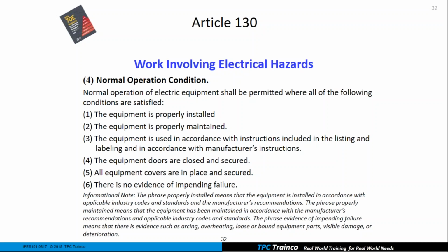Number 3 is the brand new one, and if you're familiar with the National Electrical Code, this did come out of 110.3(B) of the National Electrical Code: the equipment has to be used in accordance with the instructions that were included in the UL listing and labeling or any testing agency, and in accordance with the manufacturer's instructions. So we better hang on to those instructions because they become part of the National Electrical Code. A good example: sometimes I'll walk into an office building to perform some electrical work, and I happen to see these little electric space heaters underneath the desk. If we look at the instructions that come with that space heater, it will flat out tell us residential use only. Cannot be in a commercial or industrial building. So those manufacturer's instructions become extremely important.